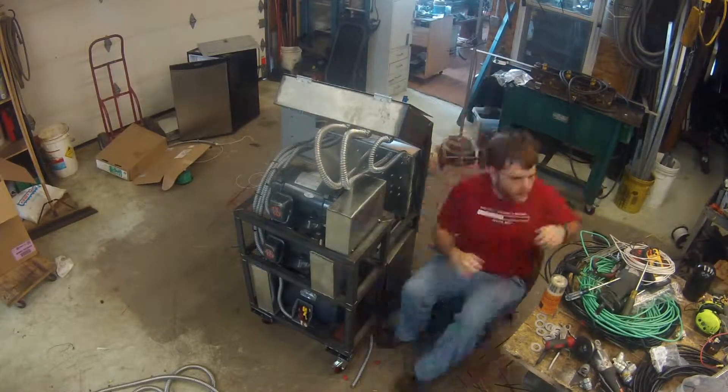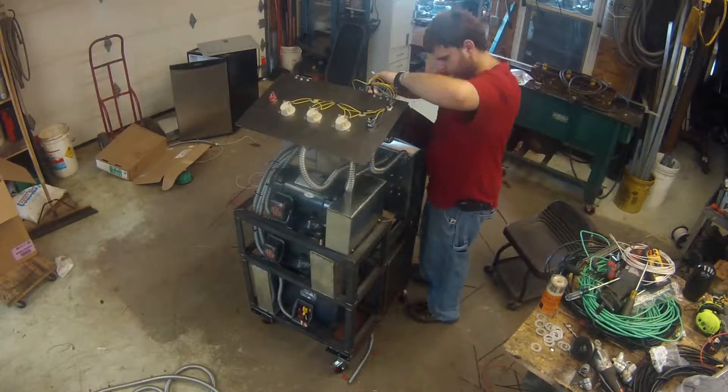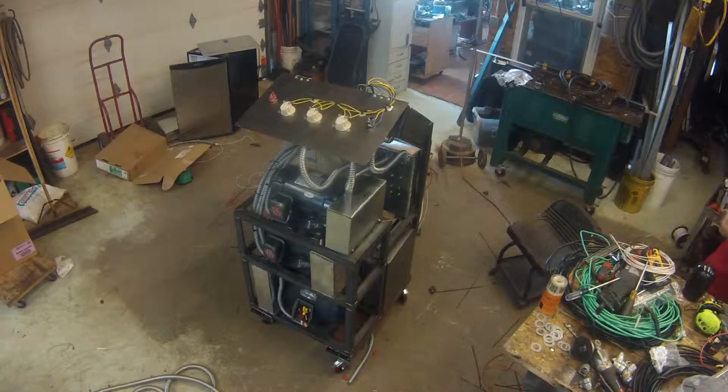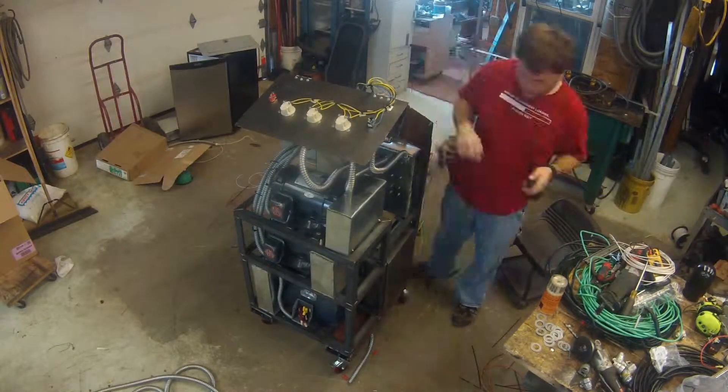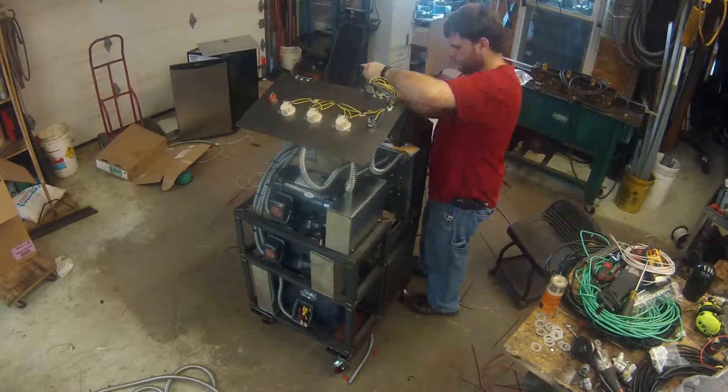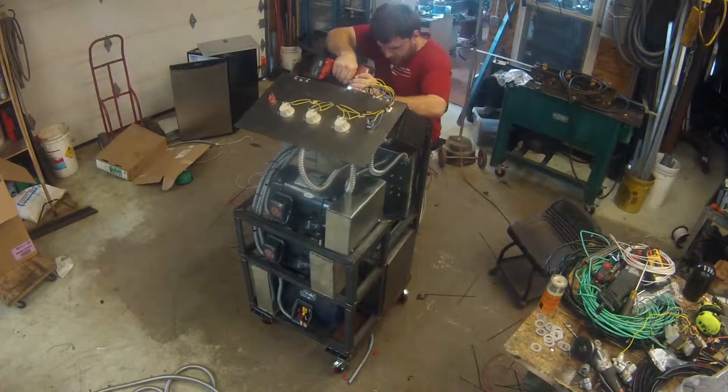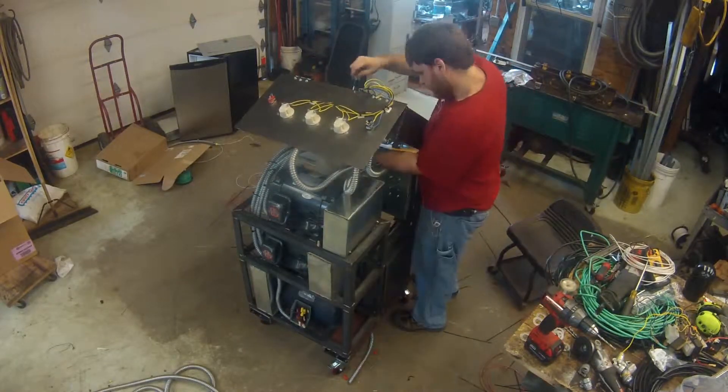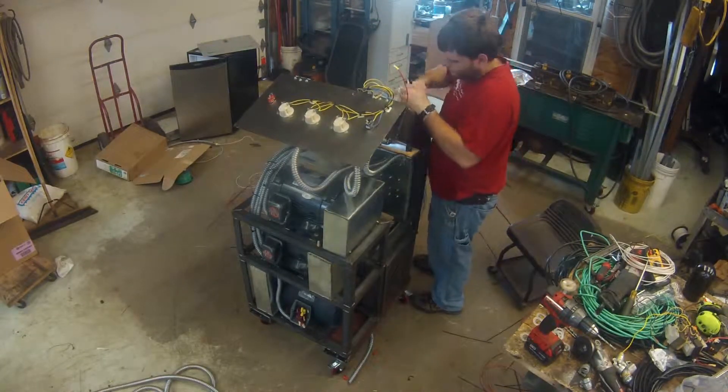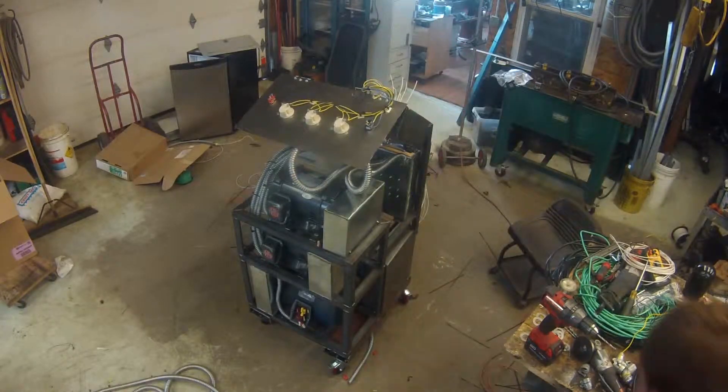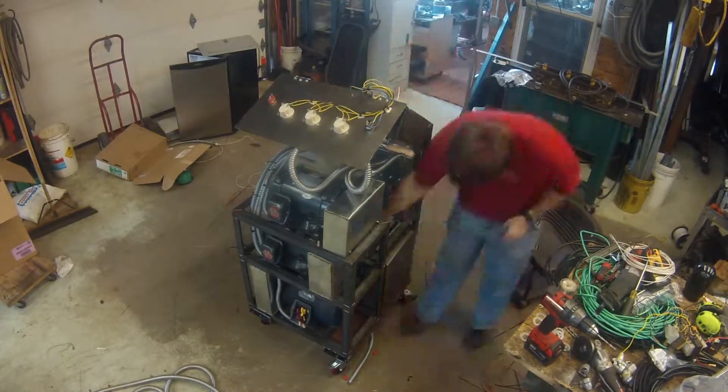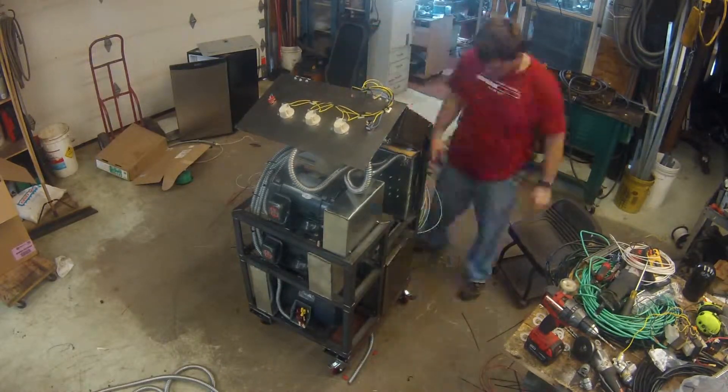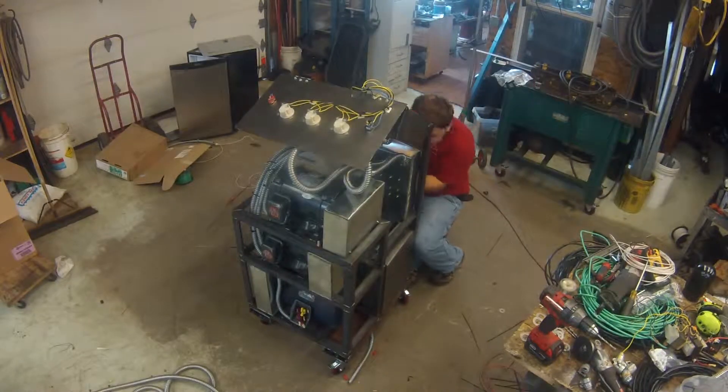This is so that I can add balancing capacitors to each motor. This will allow me to balance a lot easier and balance based on motors. Actually right now what I have is one of the motors has a ton of capacitance on it. This jumps the voltage, basically skyrockets the voltage past 300 volts no load. When I run my mill it drops down to around 240 but if I run anything else the voltage is actually too high. I think there's a problem with my mill. I did this so that the mill can run effectively without having to run the thing at that voltage all the time.